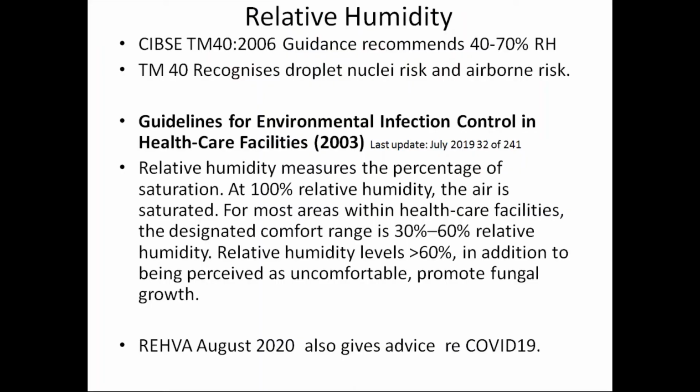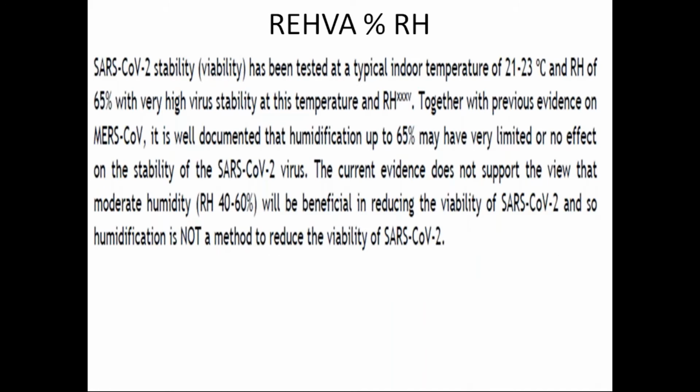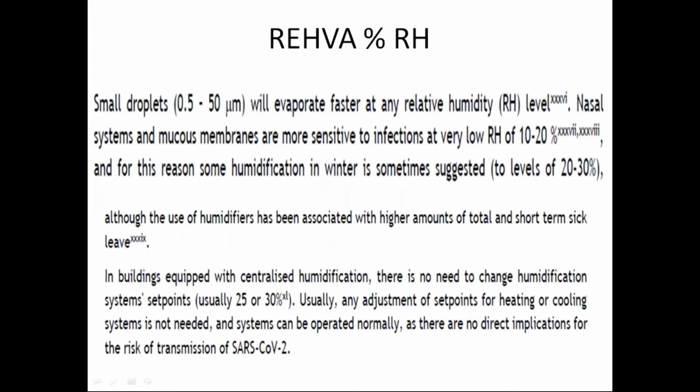This was picked up in CIBSE. It was picked up in CDC 2003. REHVA gave a slightly different view, but I believe Stephanie Taylor's research is wider bandwidth, and they're not exactly saying the same thing. So REHVA do pick up on this, on humidity. And in this slide, they are saying very similar issues. And really, we want to try and keep humidity above 25 to 30%, maybe a higher level of 70.